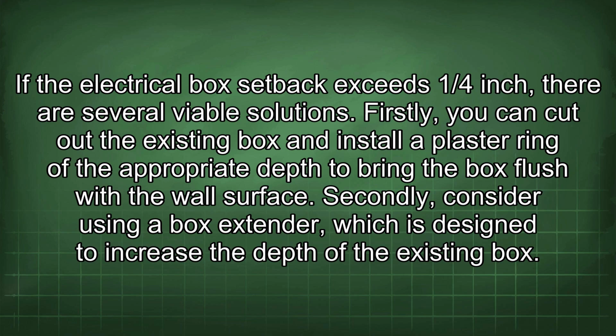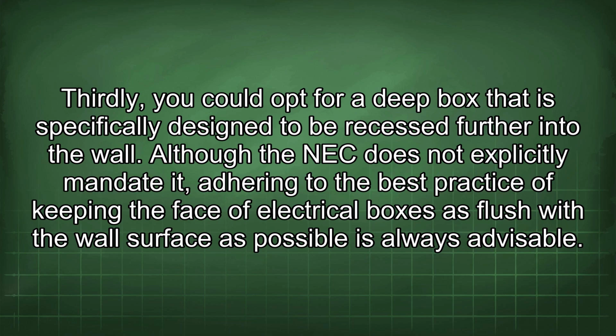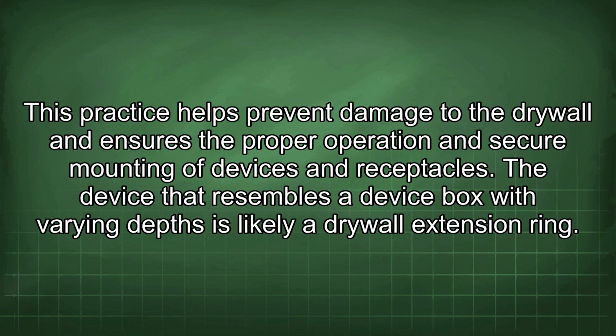Firstly, you can cut out the existing box and install a plaster ring of the appropriate depth to bring the box flush with the wall surface. Secondly, consider using a box extender, which is designed to increase the depth of the existing box. Thirdly, you could opt for a deep box that is specifically designed to be recessed further into the wall. Although the NEC does not explicitly mandate it, adhering to the best practice of keeping the face of electrical boxes as flush with the wall surface as possible is always advisable. This practice helps prevent damage to the drywall and ensures the proper operation and secure mounting of devices and receptacles.